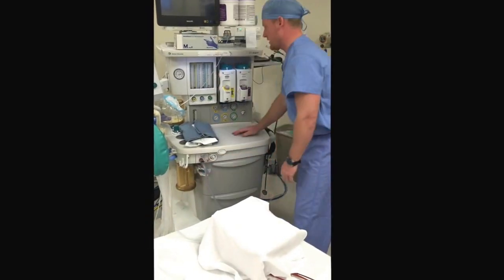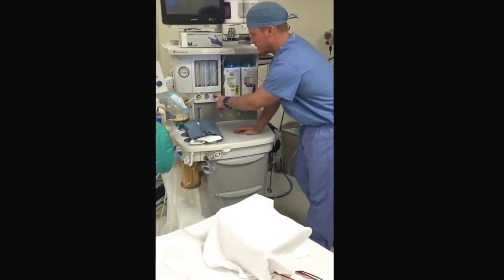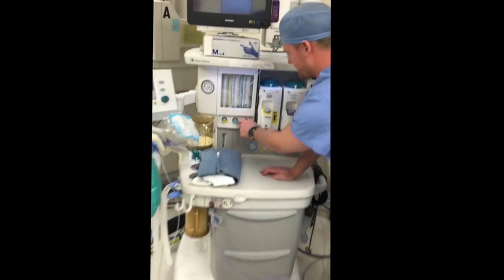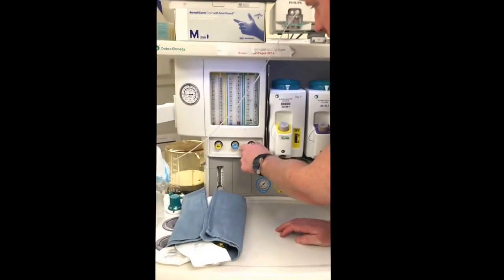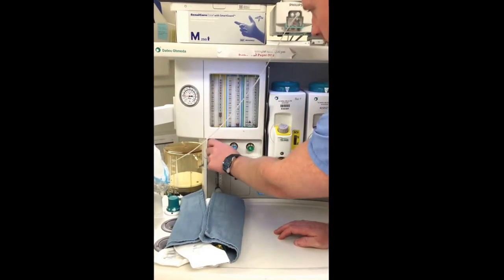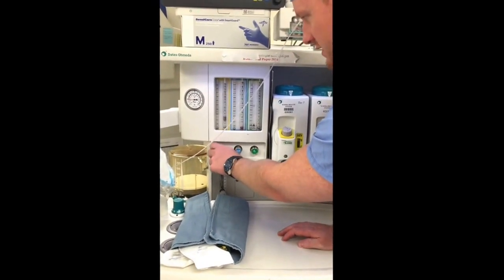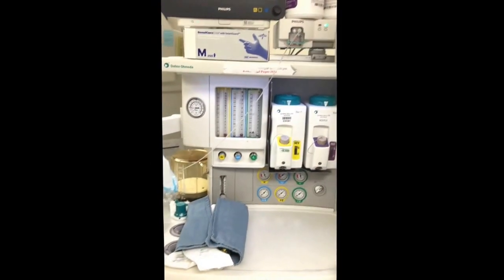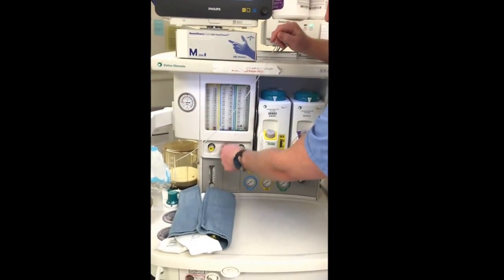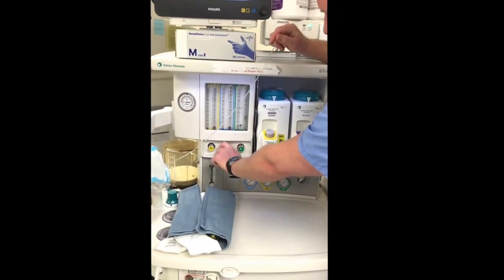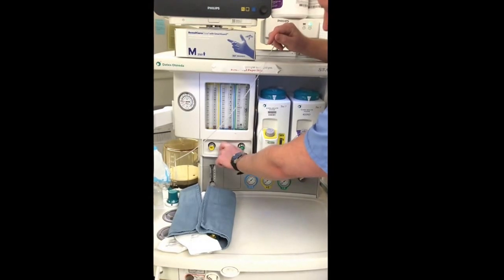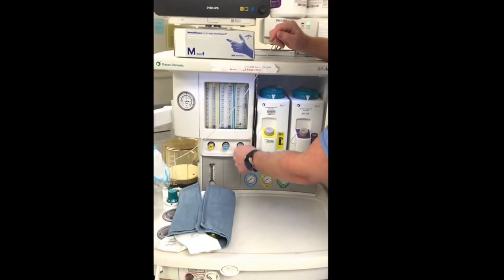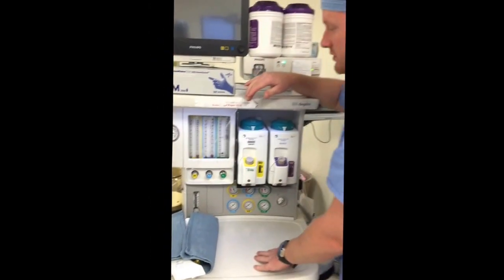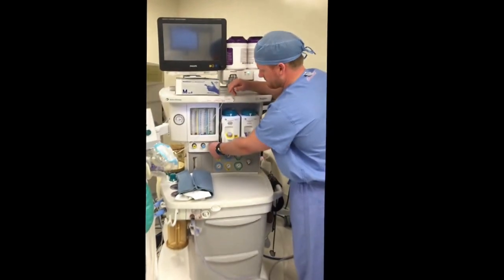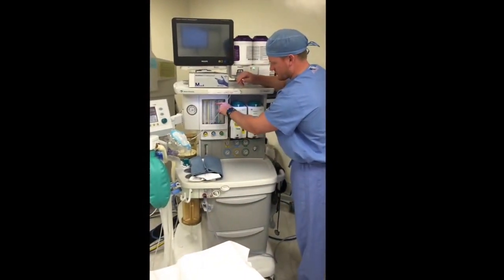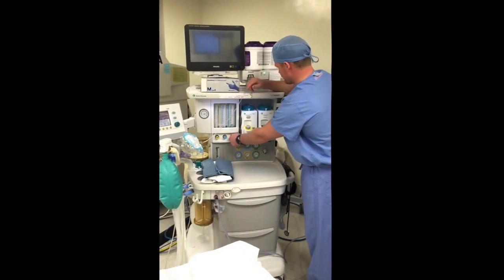The next thing you can check is properly functioning flow meters. So your oxygen, air, and in this machine we don't have nitrous, but you would try to deliver a hypoxic mixture to the patient, and as you see, as I turn nitrous, oxygen automatically goes up, so it won't let you deliver a hypoxic mixture to the patient. Ordinarily the nitrous would move up with the O2.